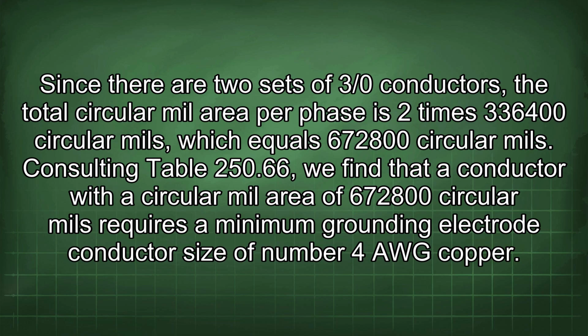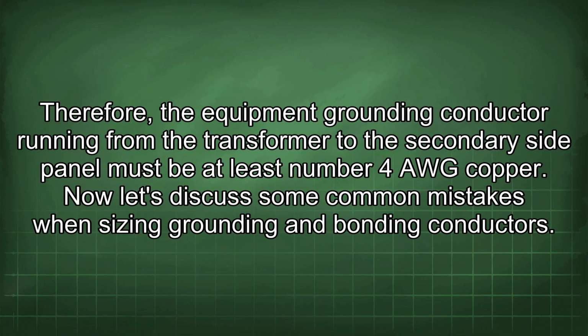Consulting table 250.66, we find that a conductor with a circular mil area of 672,800 circular mils requires a minimum grounding electrode conductor size of number 4 AWG copper. Therefore, the equipment grounding conductor running from the transformer to the secondary side panel must be at least number 4 AWG copper. Now let's discuss some common mistakes when sizing grounding and bonding conductors.